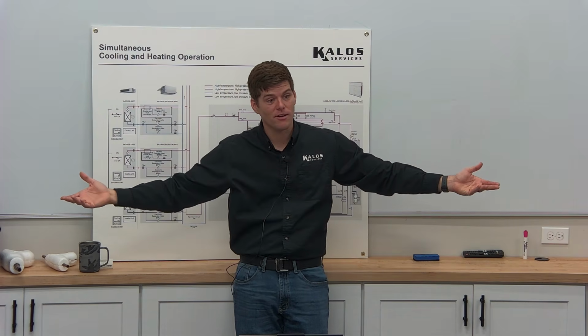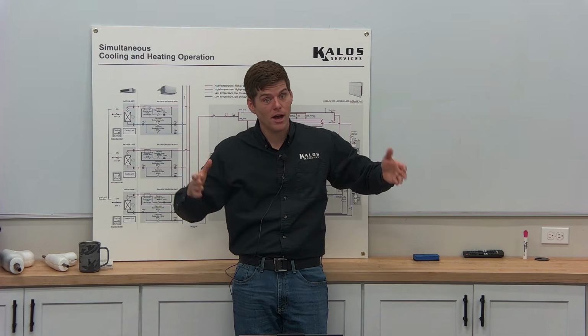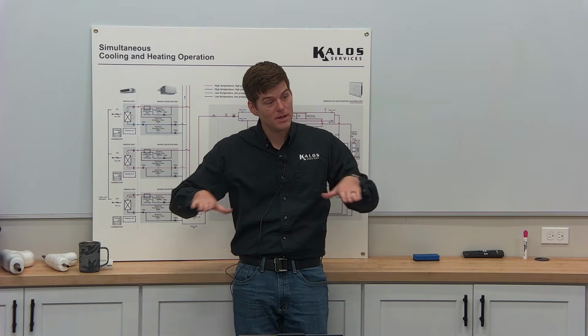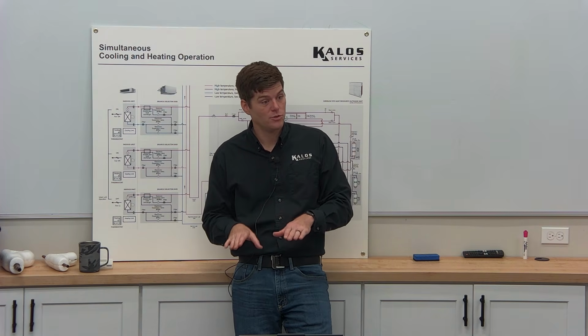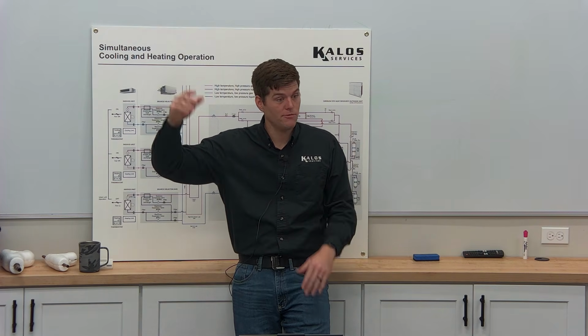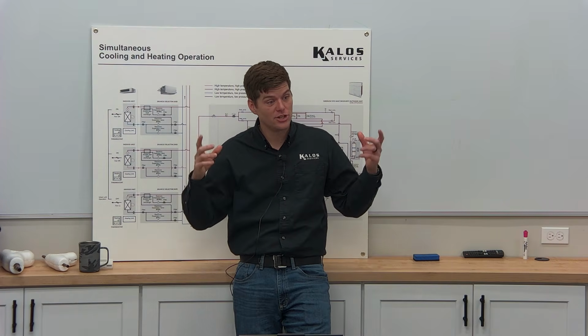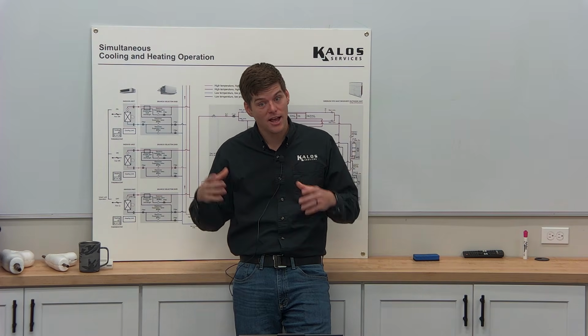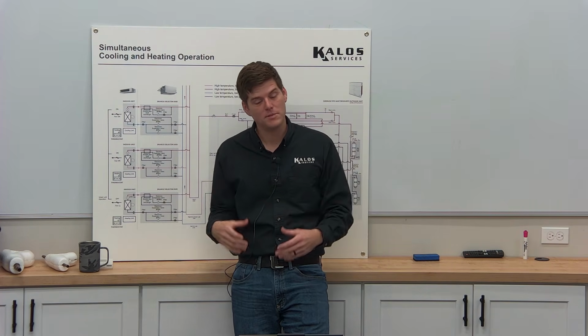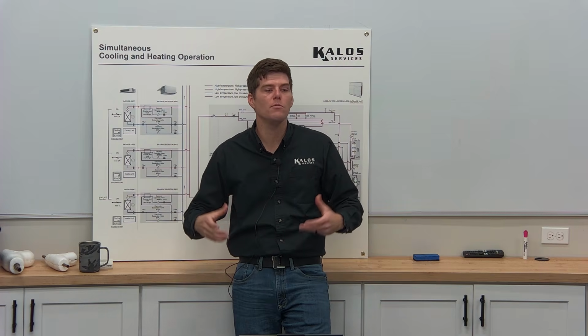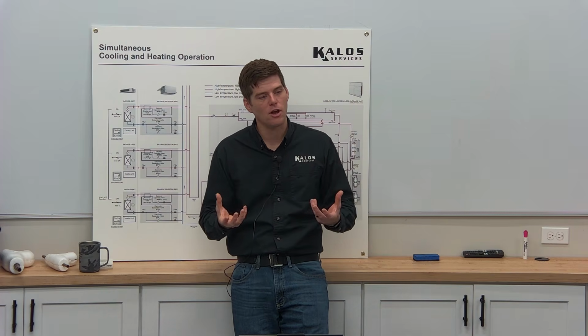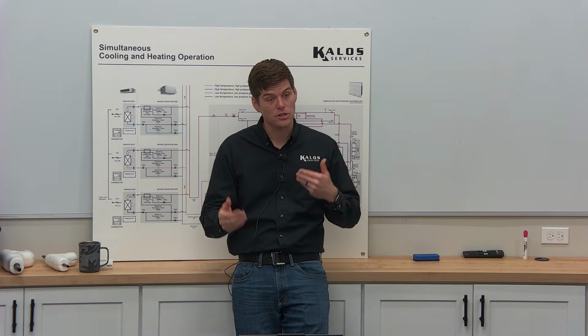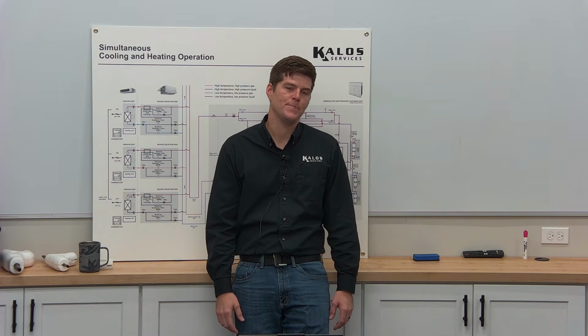It's the variable part, right? Certain models like the 8-ton would limit its compressor speed top envelope, so it can't go over a specific speed. You'll find the higher the tonnage, it has actually higher fan speeds, it has higher compressor revolutions, sometimes it has a larger compressor, so they're just moving more refrigerant, moving more airflow across that actual outdoor heat exchanger to deliver that 14 tons of capacity.